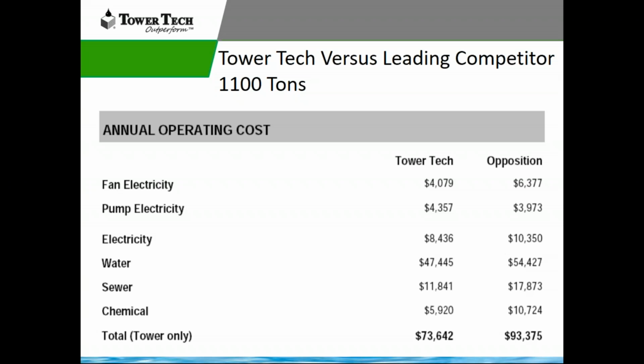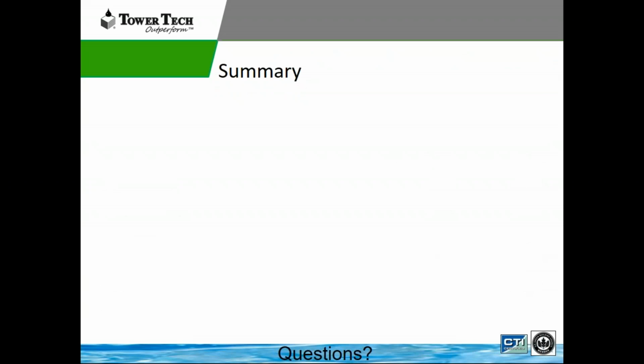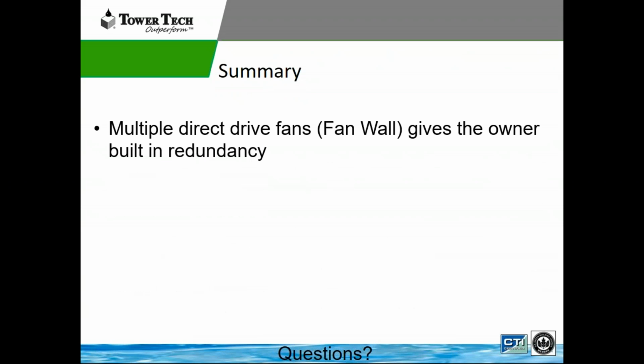And in this case, it was somewhat of a payback. In most cases, we'll find a payback of 3 to 5 years, and if it operates year round, it's much less than that. So, from a summary standpoint, we have multiple direct drive fans, so we give the owner built-in redundancy. This is a key. There are no emergency phone calls, right?